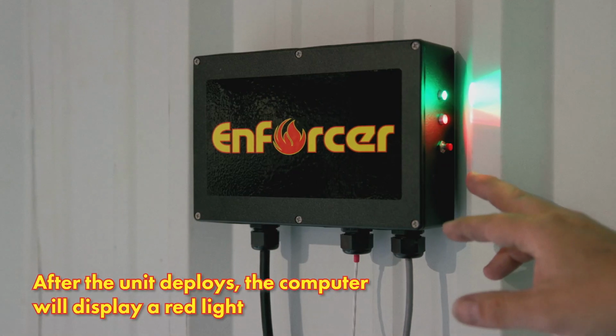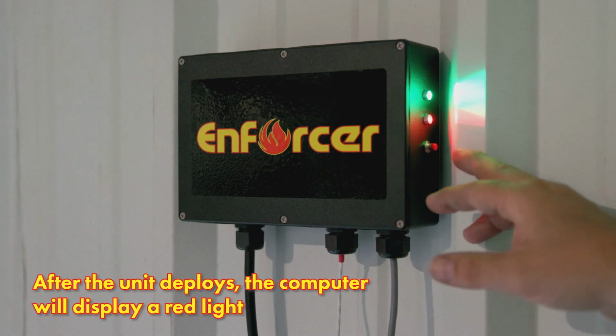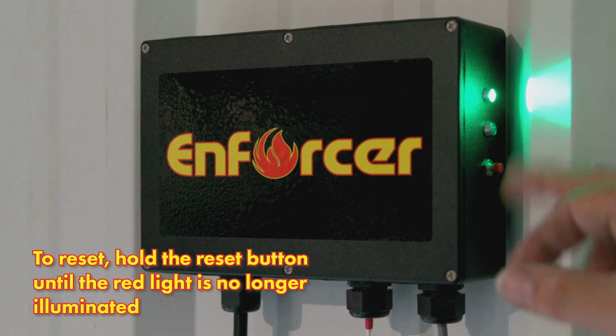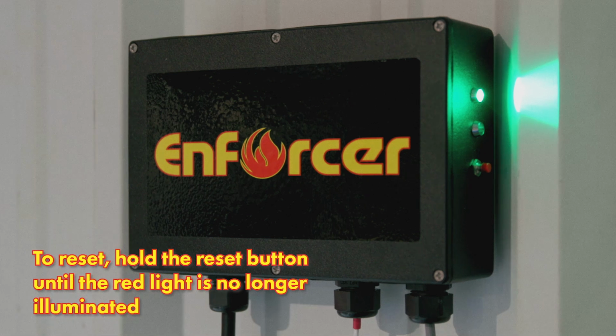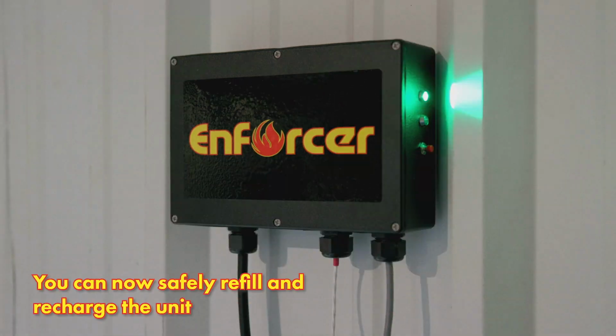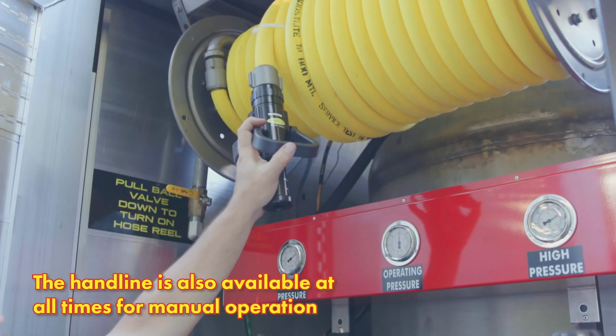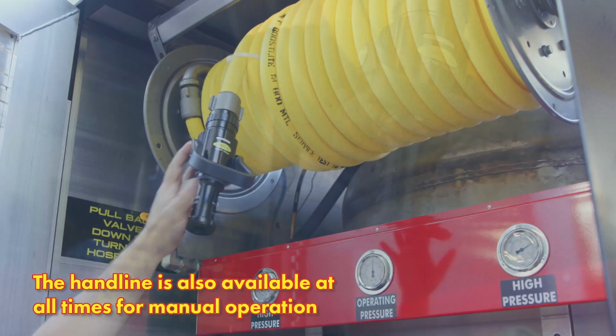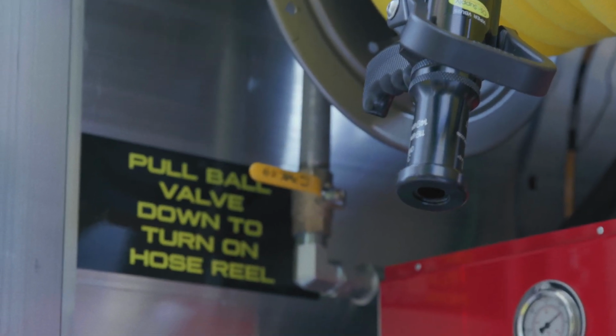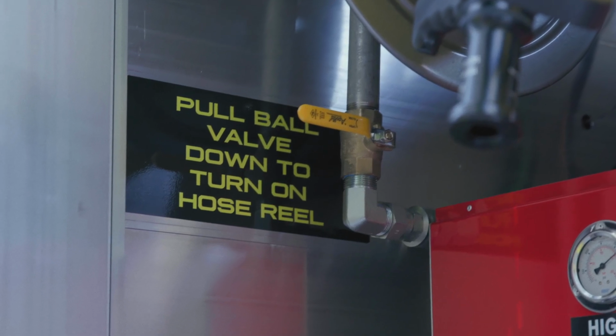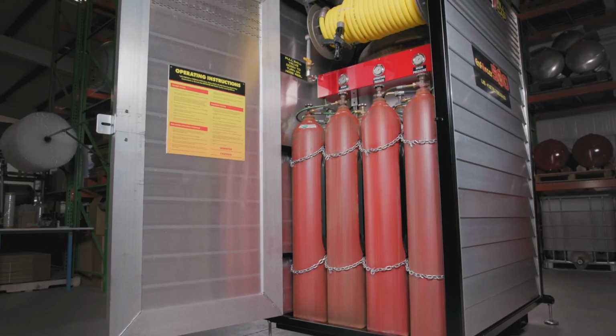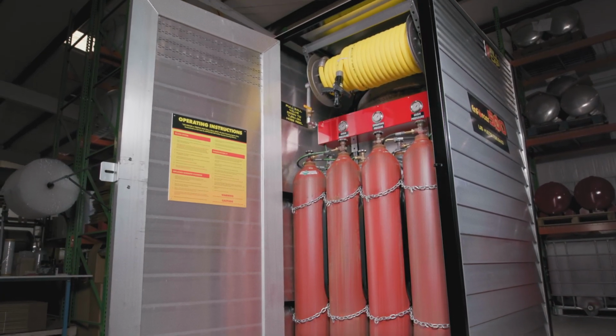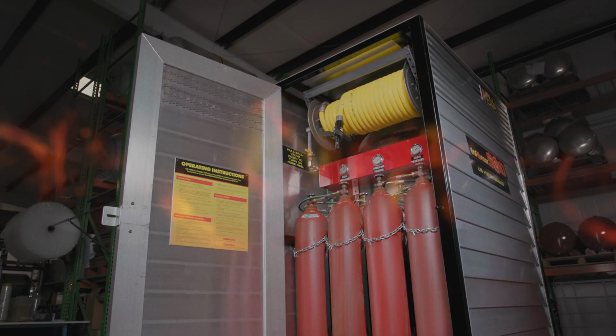After the unit deploys, the computer system will display a red light. Hold the reset button down until the light is no longer illuminated to reset the system. You can now safely refill and recharge the unit. The hand line is also available at all times for manual operation. To activate the hose reel, simply pull the ball valve down. Refer to your manual for more detailed instructions, and as always, contact us with any questions or concerns.